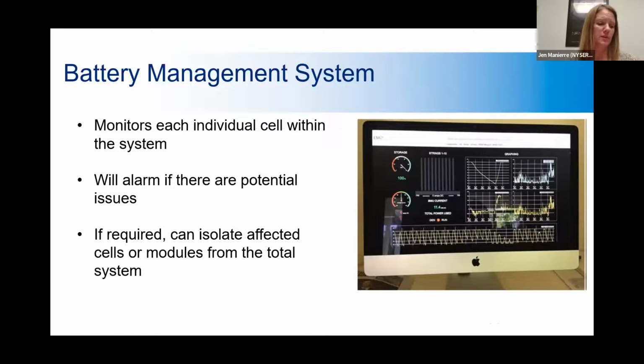We went through the building blocks of an energy storage system a couple slides ago, the cells, the modules, the racks. The one additional thing all these systems are going to have, it's not just batteries strung together, and that's it, put energy in, take it out. They're also going to have a battery management system. And these systems can monitor all the way down to the individual cell level, even in those larger utility scale systems, and make sure that all of the individual battery cells are operating within the proper temperatures and things like that, so that nothing will go wrong.